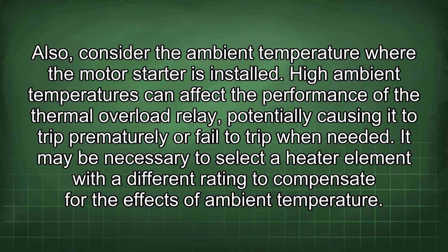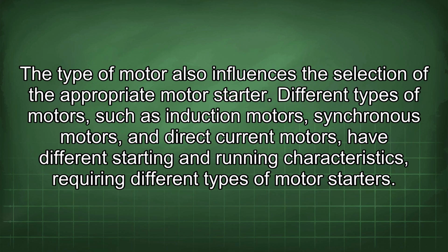Also, consider the ambient temperature where the motor starter is installed. High ambient temperatures can affect the performance of the thermal overload relay, potentially causing it to trip prematurely or fail to trip when needed. It may be necessary to select a heater element with a different rating to compensate for the effects of ambient temperature. The type of motor also influences the selection of the appropriate motor starter. Different types of motors, such as induction motors, synchronous motors, and direct current motors, have different starting and running characteristics, requiring different types of motor starters.